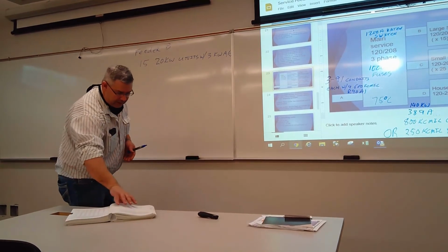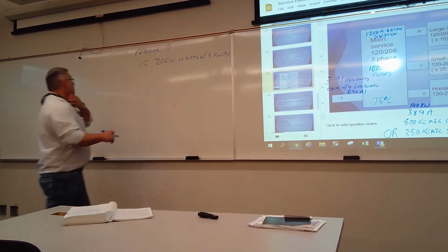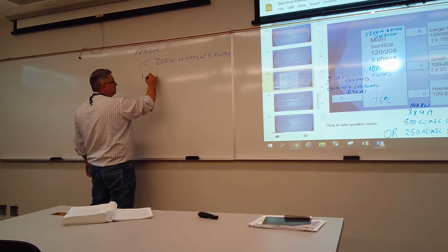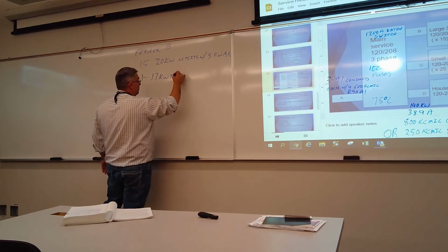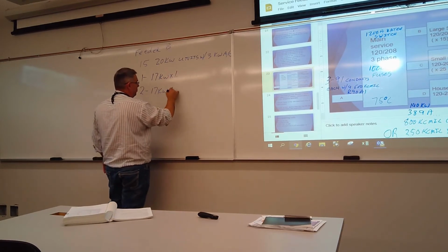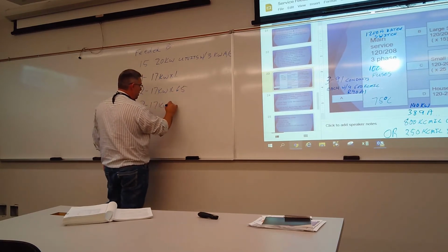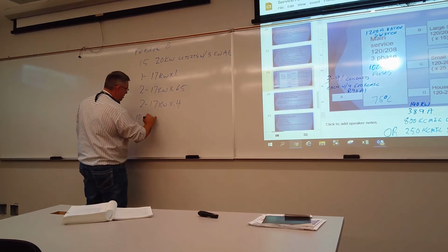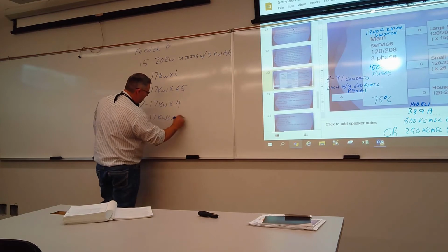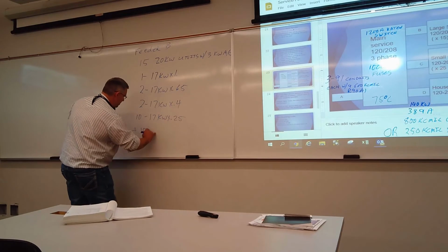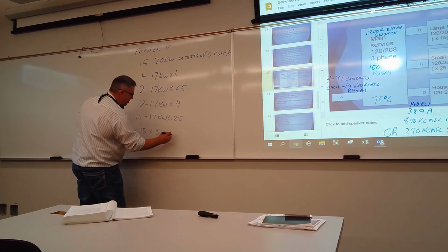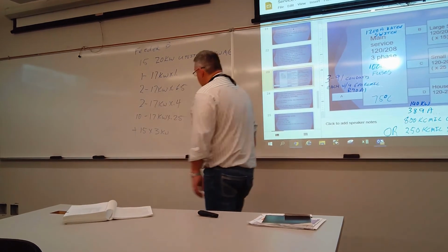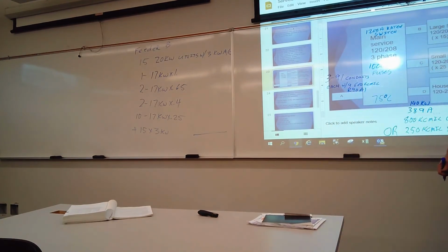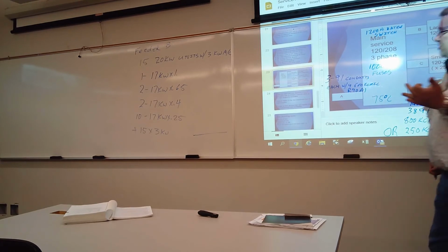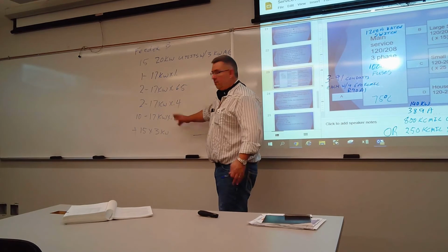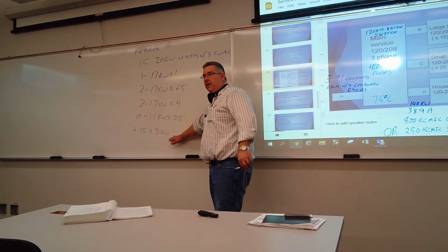We're going to go right back through 8-2023. We're going to take the AC out, so that means we've got one 17 kilowatt times 100%, two 17 kilowatt times 0.65, two 17 kilowatts times 0.4, 10 17 kilowatts times 0.25, plus 15 times 3 for the air conditioning. That's what that calculation looked like, right? First unit at 100%, the next two at 65%, next two at 40%, the next 15 at 25%. We've only got 10. And then the air conditioners loaded, added back in at 100%.